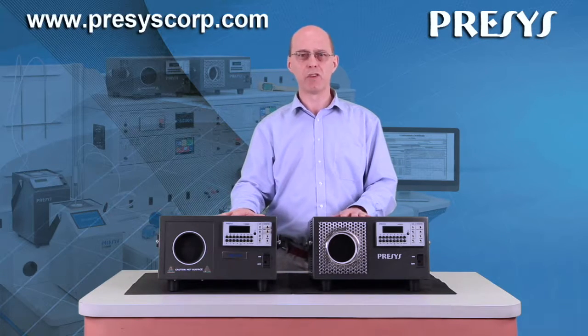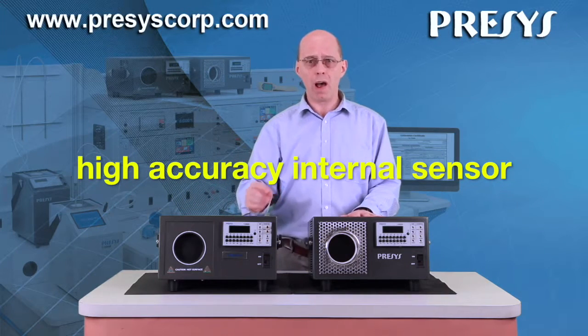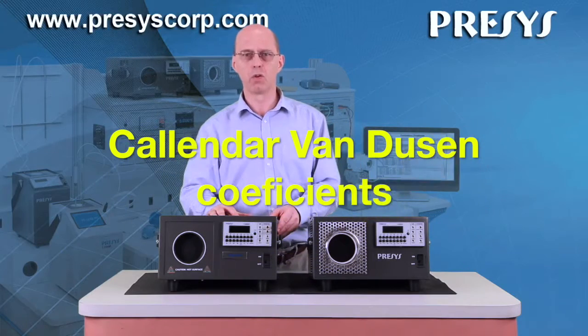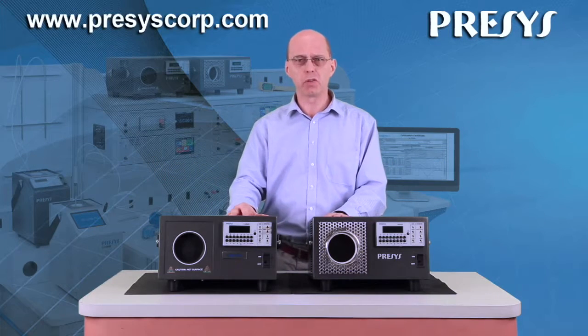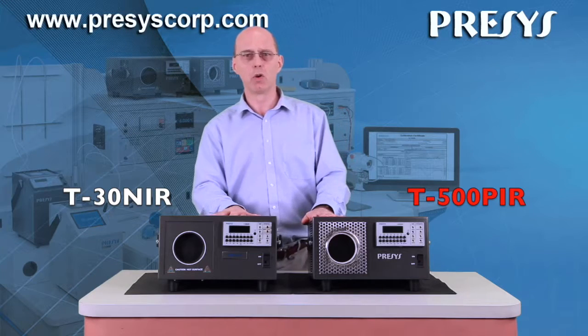These calibrators have a high accuracy internal sensor. But when a higher accuracy is needed, an external sensor can be used with setting of the Callendar-Van Dusen coefficient of the sensor on the calibrator controller. These features make the T-500PIR and T-30NIR cost-effective infrared calibrators with best performance in their category.